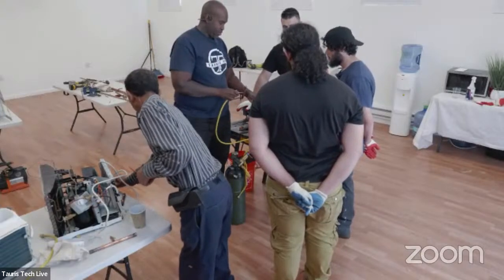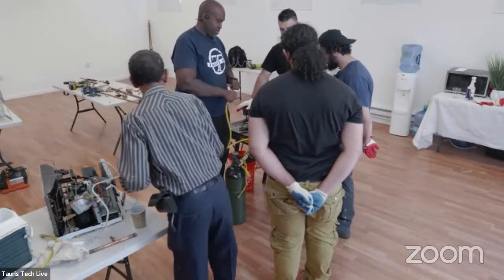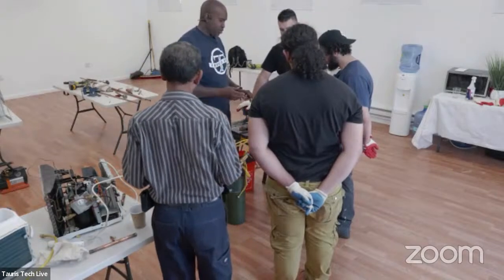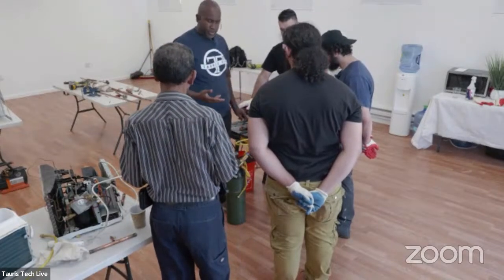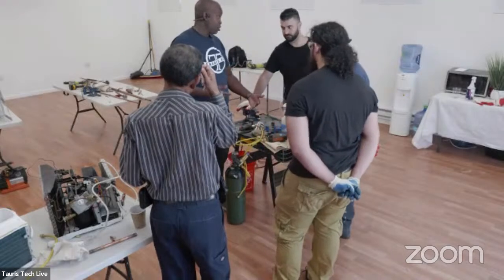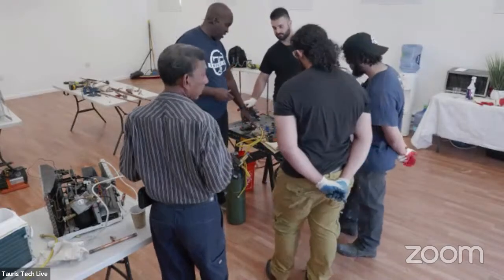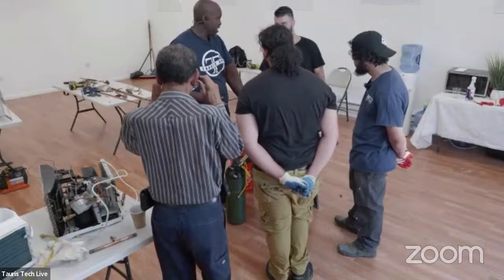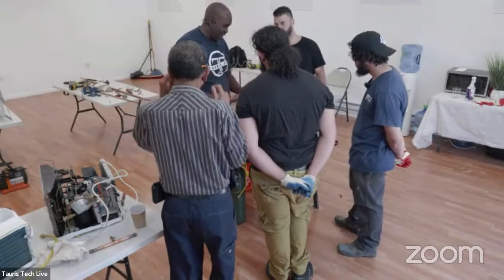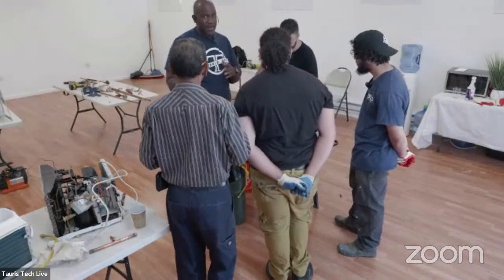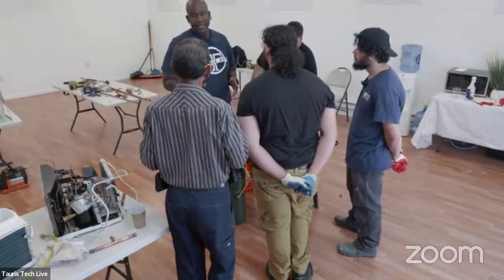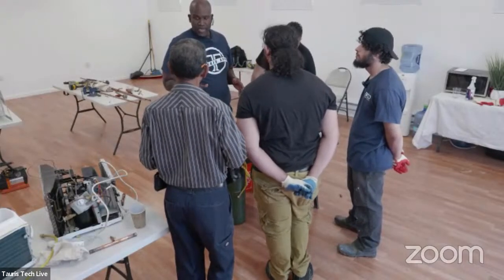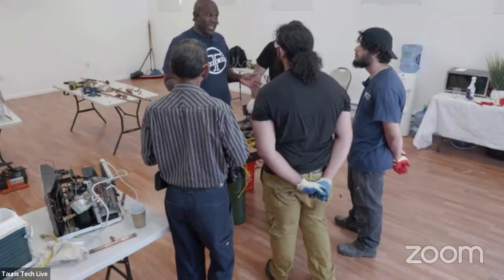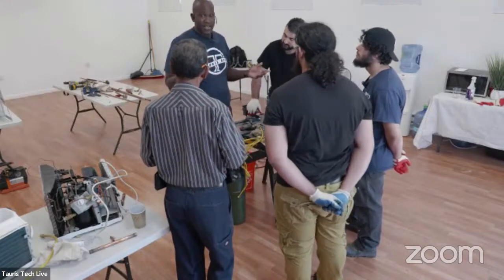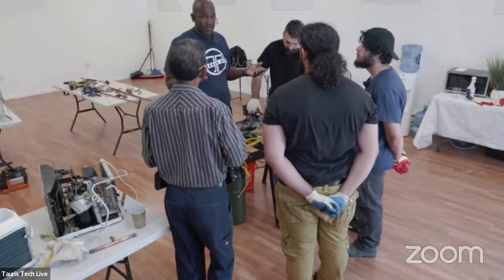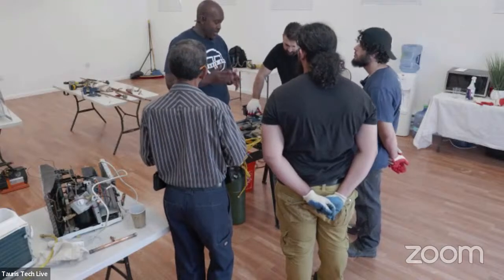Oh, there's my pressure, okay, so it's holding. So what you want to do is check, what was the pressure when you did it the first time? Because if you put 400 in and now it's at 100, then you know you have a leak. That's what happens with the machines. When people don't go through the proper procedure, everything might be working when you leave, and then the client calls saying it's not working, because everything leaked out. You have to make sure everything's going to hold.